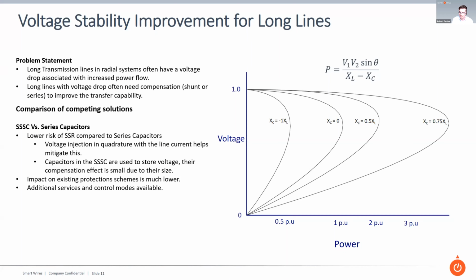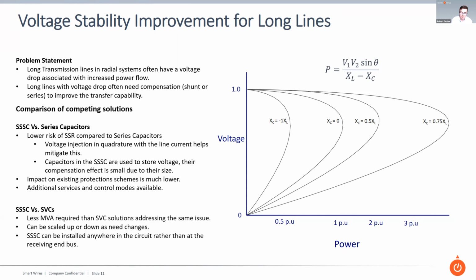Instead of just providing bulk voltage injection, they can react dynamically to things going on in the grid and provide additional services. Comparing it to the SVCs that were proposed, there was less MVA required. So the SVCs had to have a much larger installation on site than compared to an SSSC solution. The SSSC can be scaled up and scaled down a little bit more easily than the SVC, as the components use series reactors and series capacitors.